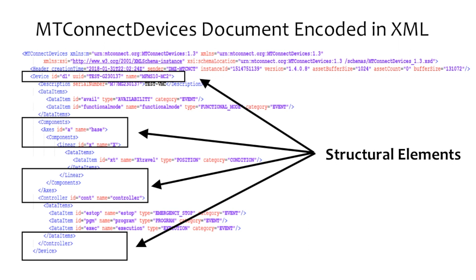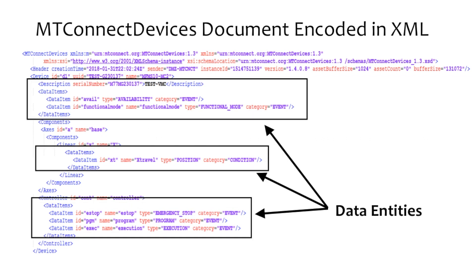In addition to defining the various parts and pieces that describe a piece of equipment, the information model also provides an ontology, or set of rules, that defines the relationship between the various sub-parts of a piece of equipment. The ontology information is a vital component that establishes a standardized approach for manufacturers to describe their equipment, which is fundamental for creating structured data. Data entities are used to describe each piece of data published by the equipment, organized into one of three categories: samples, events, and conditions.